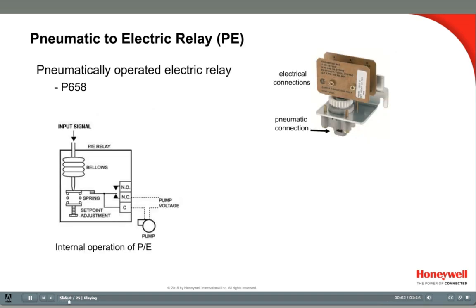Another useful electric interface is the pneumatic-to-electric relay, commonly referred to as a PE relay. Inside, it has a bellows that is operated by a pneumatic pressure signal. The bellows moves to make or break electric contacts. PE relays are used to control electric devices using pneumatic control logic. The relay has an adjustable set point and can be set to make or break contacts at any desired pressure. They can be used for on-off control of fans and pumps, energizing electric heaters, day-night control of unitary equipment, interlock functions, and control of other electrical equipment in mechanical systems.